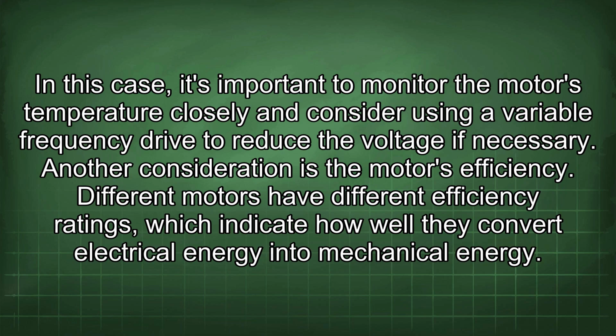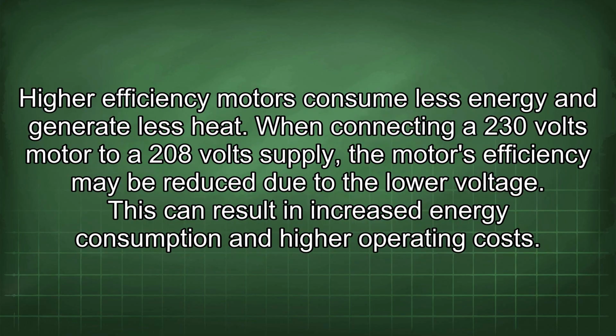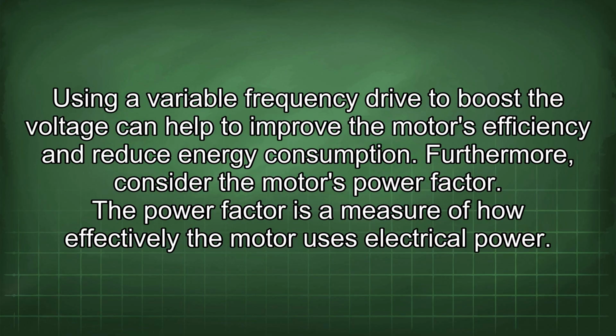Another consideration is the motor's efficiency. Different motors have different efficiency ratings, which indicate how well they convert electrical energy into mechanical energy. Higher efficiency motors consume less energy and generate less heat. When connecting a 230 volts motor to a 208 volts supply, the motor's efficiency may be reduced due to the low voltage. This can result in increased energy consumption and higher operating costs. Using a variable frequency drive to boost the voltage can help to improve the motor's efficiency and reduce energy consumption.